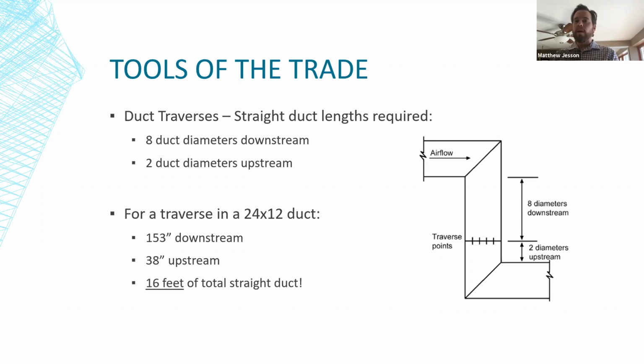That's quite a bit of distance that is sometimes not feasible for a particular duct. And bear in mind, this is for a 24 by 12 duct. That increases as you get bigger duct. It isn't always 16 feet. Now, if you can't get an ideal duct traverse, the next best thing is a non-ideal duct traverse. If you have some straight duct, you can always try to get a duct traverse in it, and you can evaluate the velocities that you read, the velocity pressures in the grid, and see if they are even enough to use as a proper measurement.